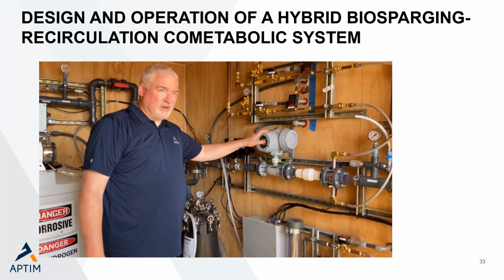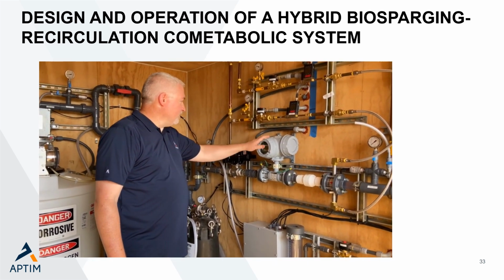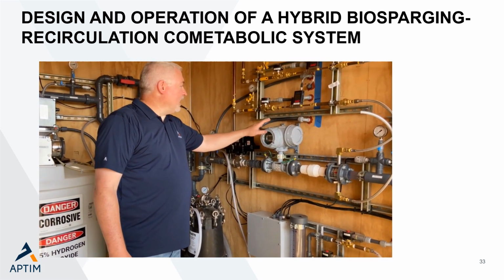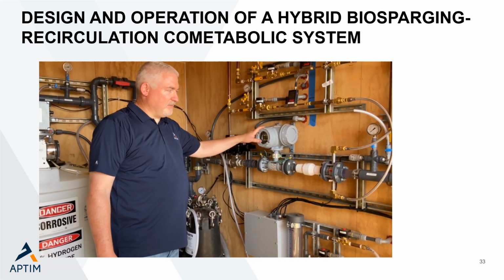This is a flow meter. Our flow set point right now is 12.5 GPM. This is a flow controller, so this communicates with our PLC. At our set point, this valve controls the flow to 12.5 GPM.